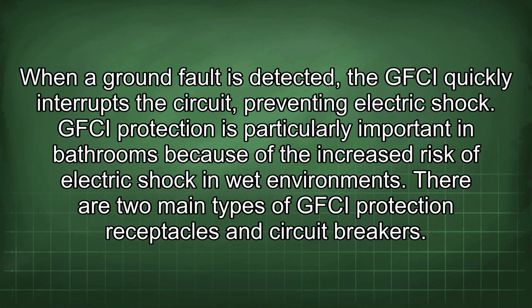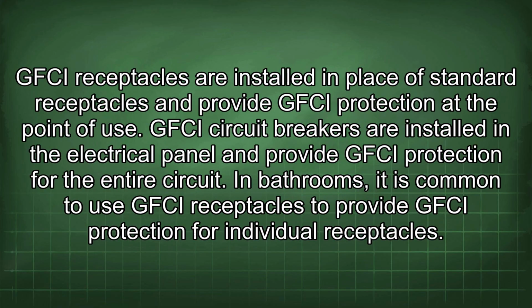There are two main types of GFCI protection: receptacles and circuit breakers. GFCI receptacles are installed in place of standard receptacles and provide GFCI protection at the point of use. GFCI circuit breakers are installed in the electrical panel and provide GFCI protection for the entire circuit. In bathrooms, it is common to use GFCI receptacles to provide GFCI protection for individual receptacles.